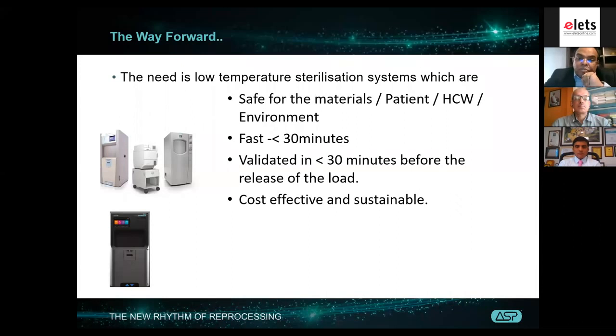An autoclave will not be able to do that, nor will a steam sterilizer, because the water or steam presence and high temperature will actually discharge the charges in the system. An ETO machine will also not be able to do that, because it needs a huge time for aeration, at least 12 hours. So that is also a challenge.